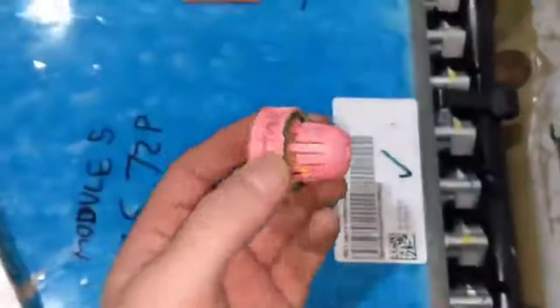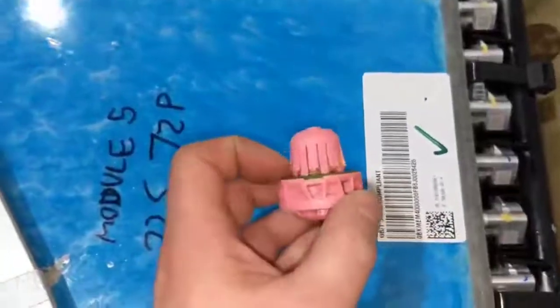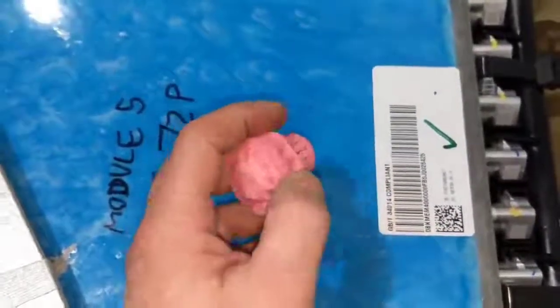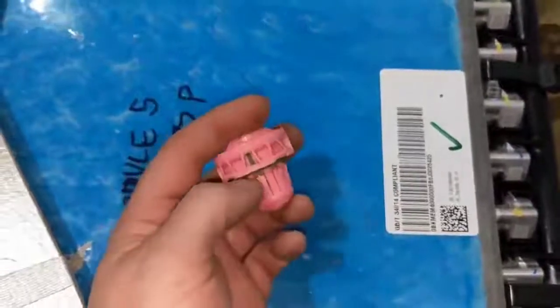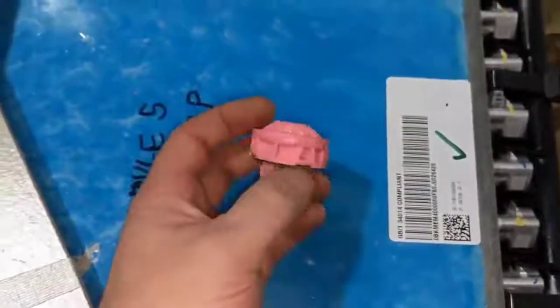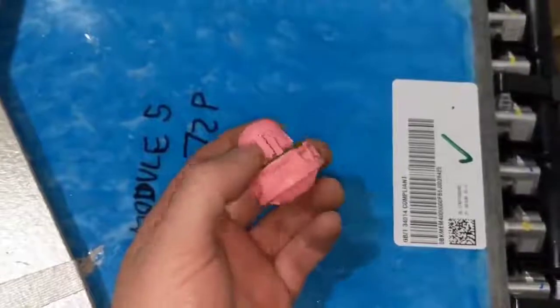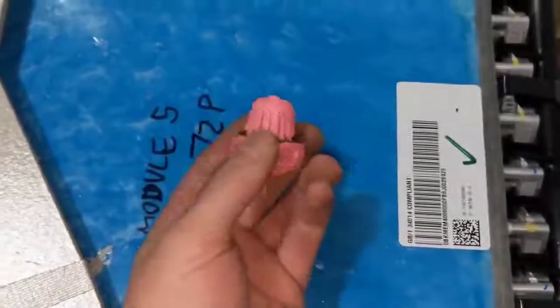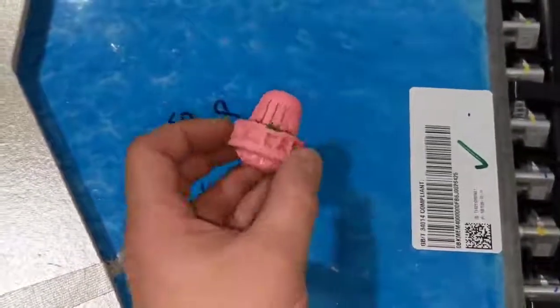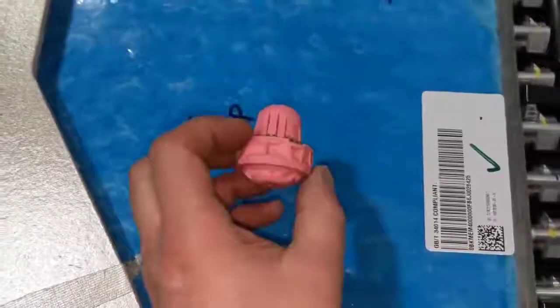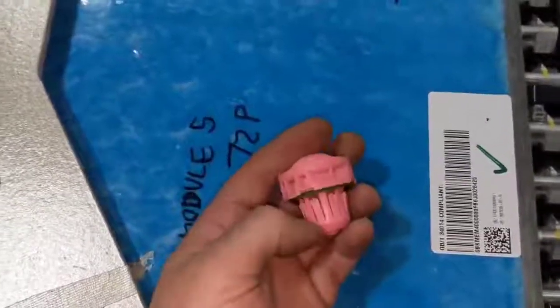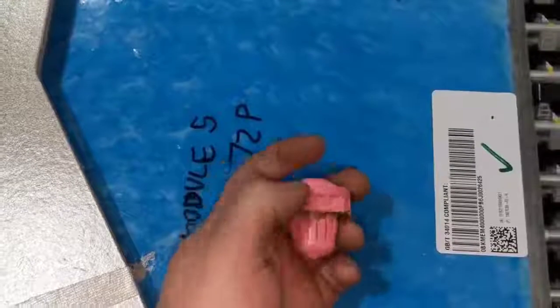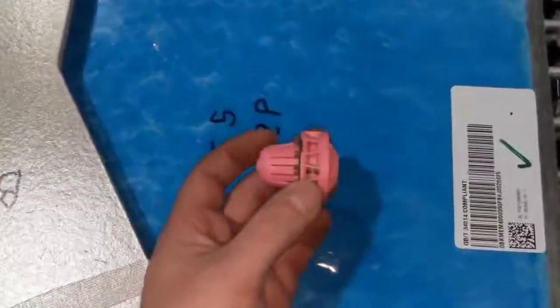Can't get that one out, but we'll pull one out back here — I've already removed it. This is an interesting device. Inside there's an O-ring, and it's held closed with a ring made out of cellulose that dissolves when in contact with water, liquid, Brondo, urine, whatever. The powerful spring in here will pop this open and allow the liquid inside the pack envelope to drain out.